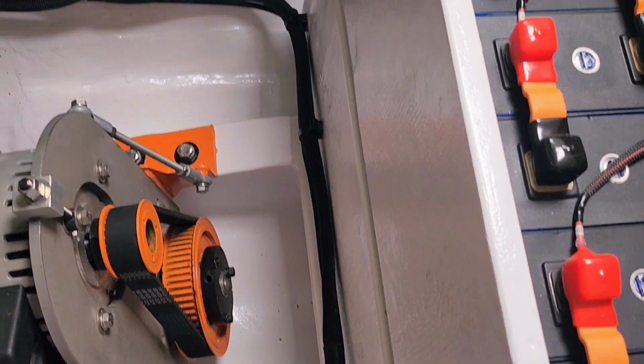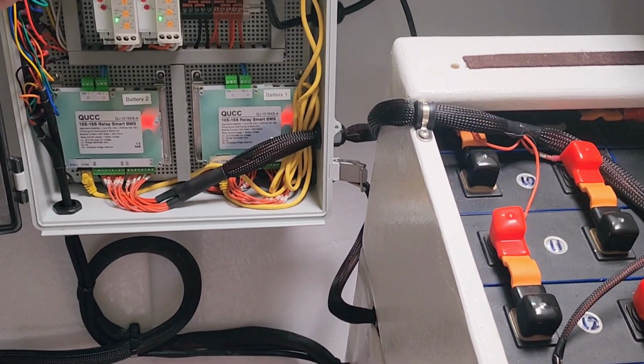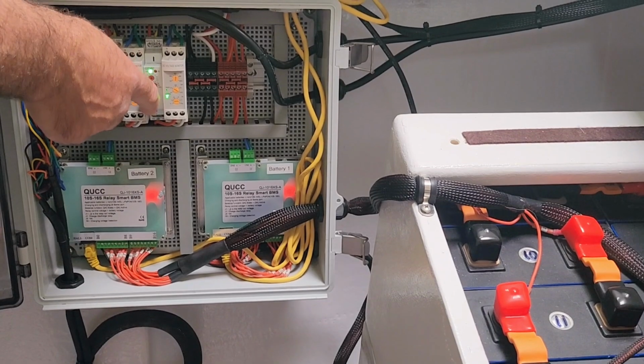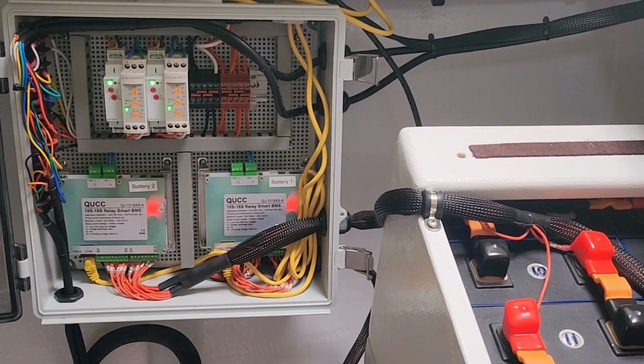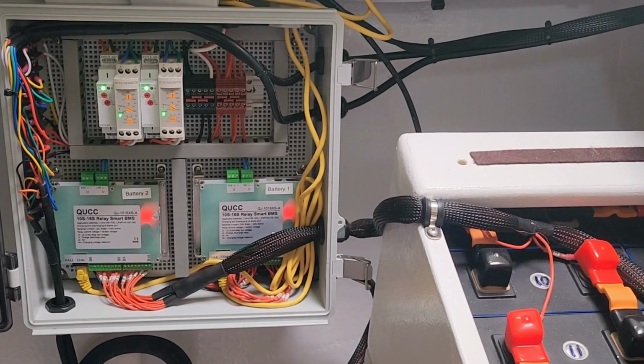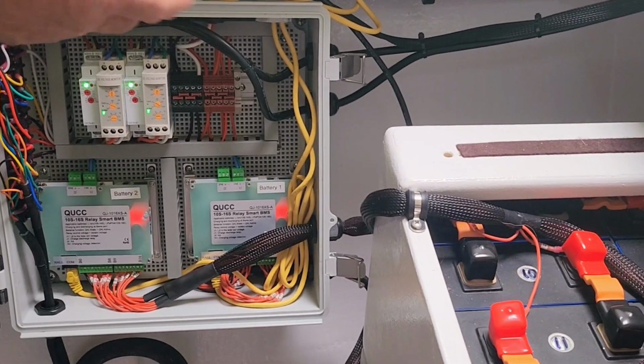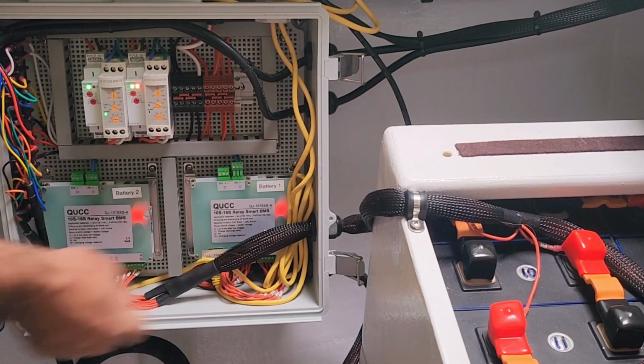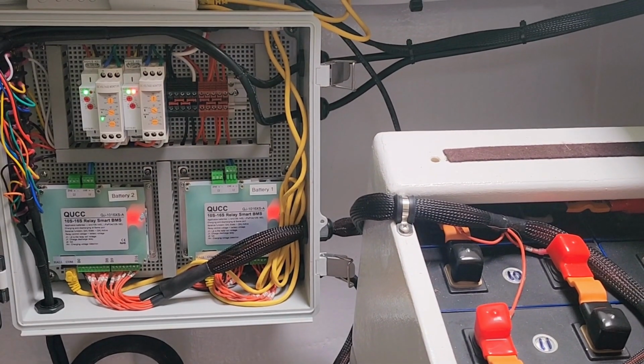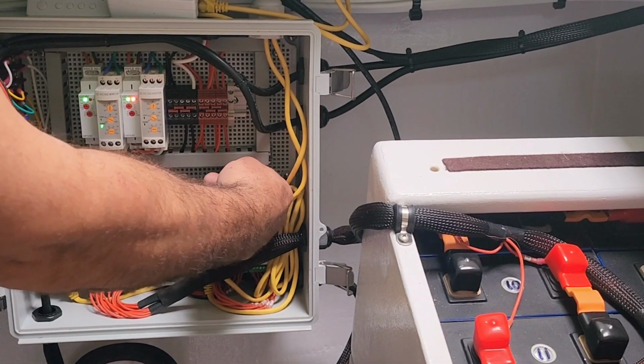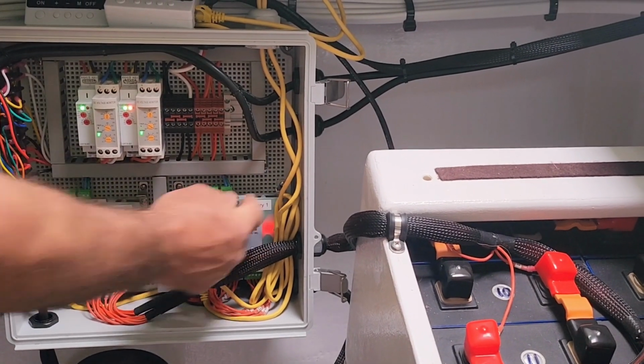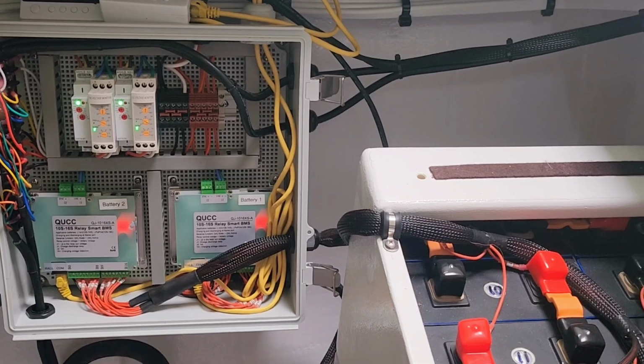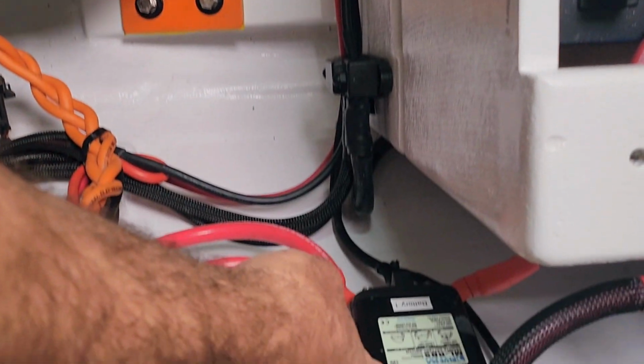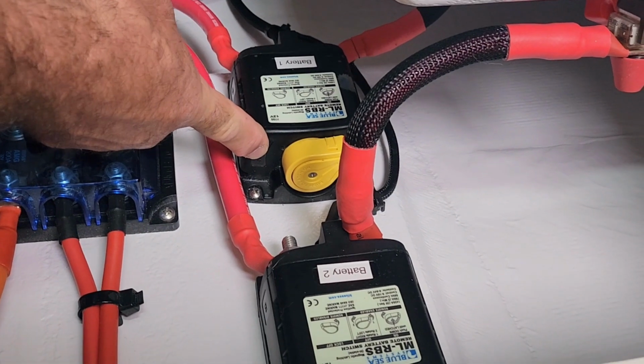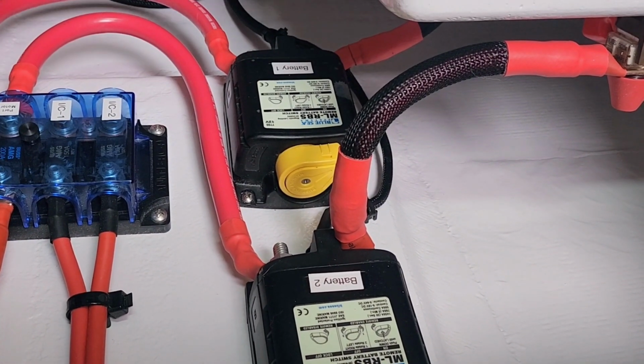These relays are also unique because they're not constantly energized. They're energized only with a momentary signal to either turn on or turn off, or to open or to close. So in the case of a fault, I'll duplicate a fault by just disconnecting this 48 volt signal. We're in alarm. My alarm panel shows that I have an alarm. Alarm's reset, but my disconnect switch is still open. And I have to come and check out what's going on inside the battery compartment.